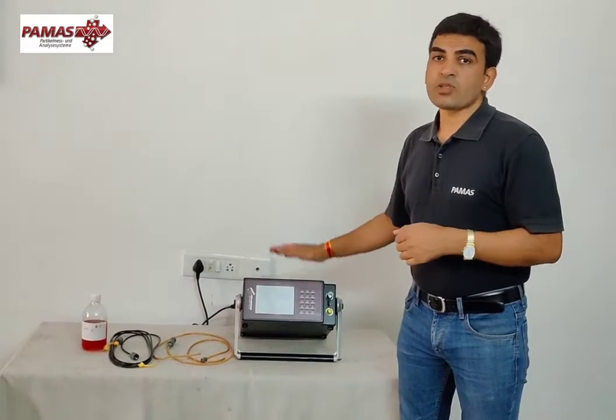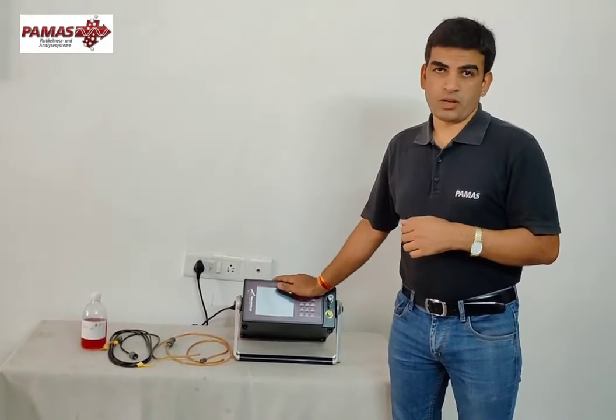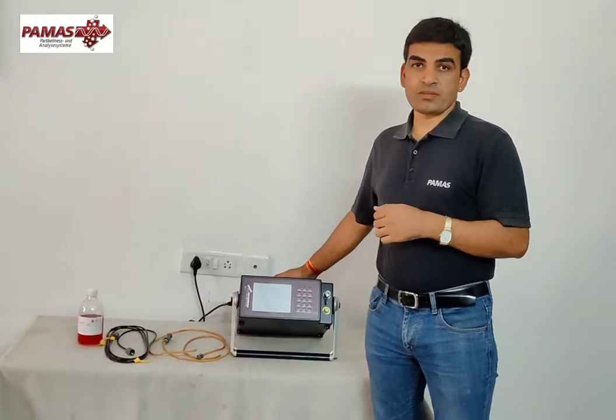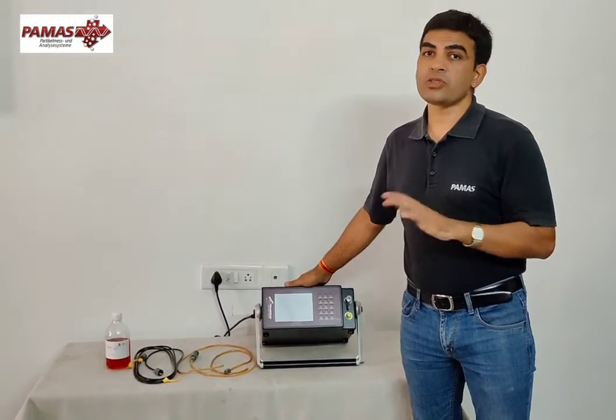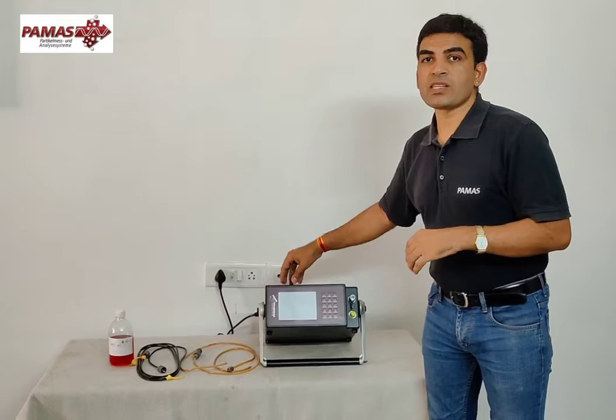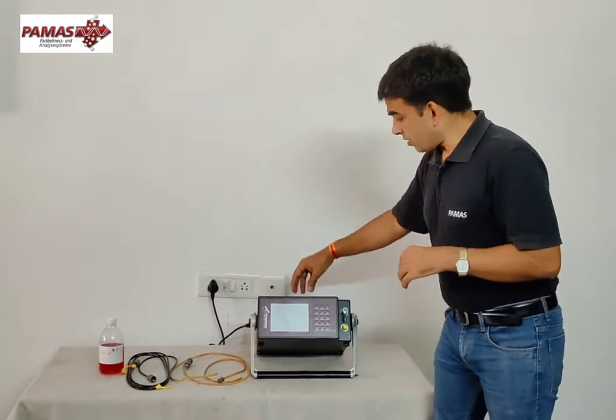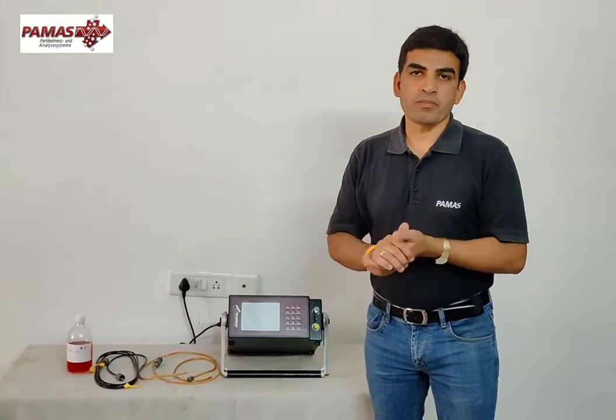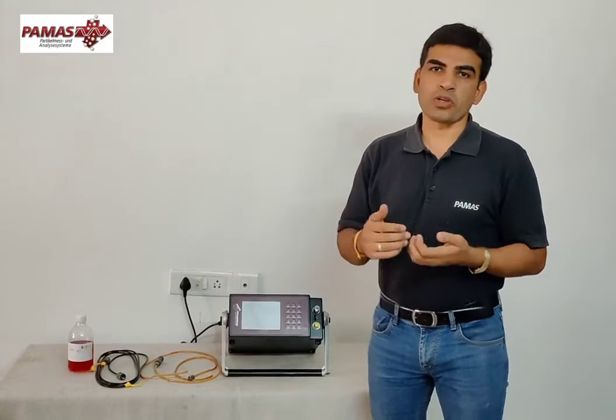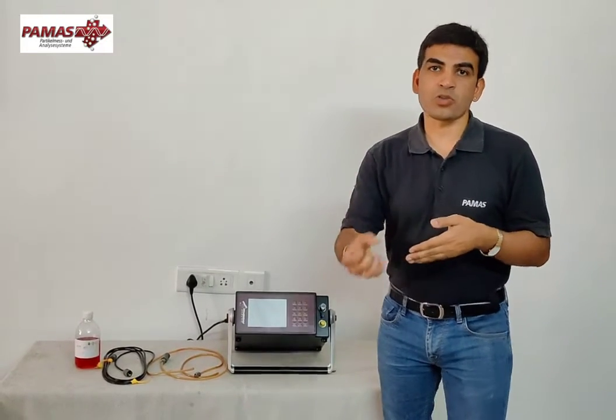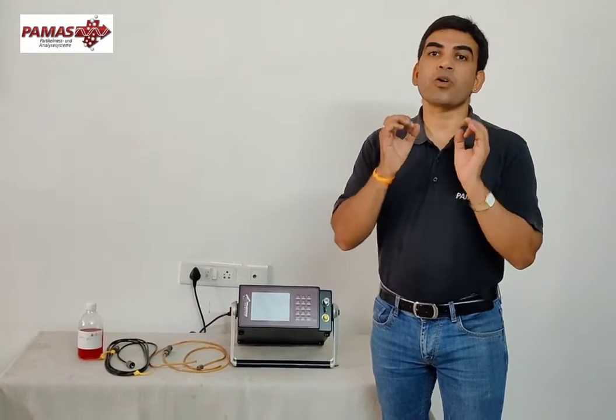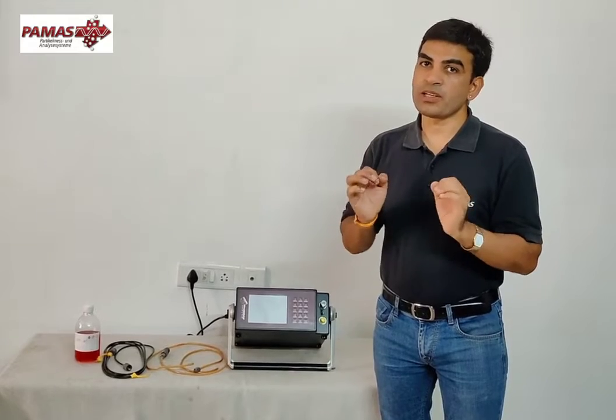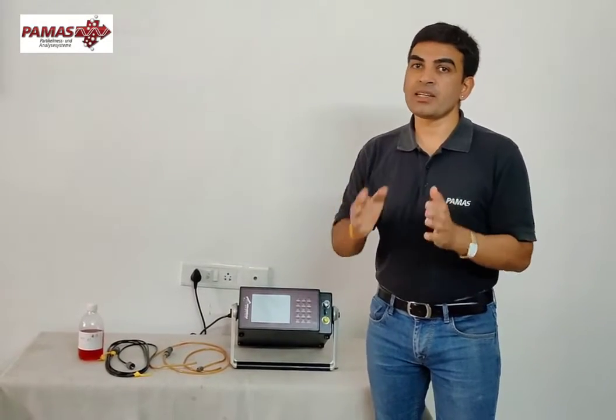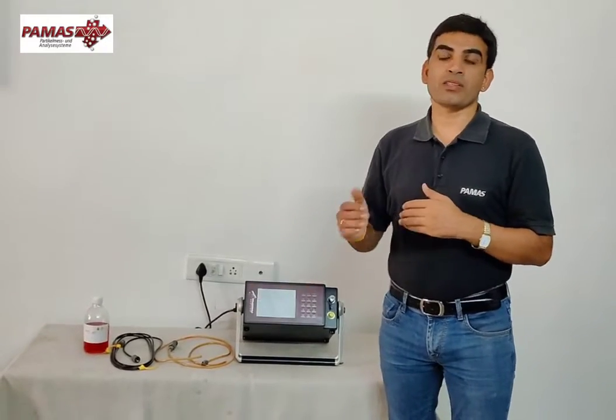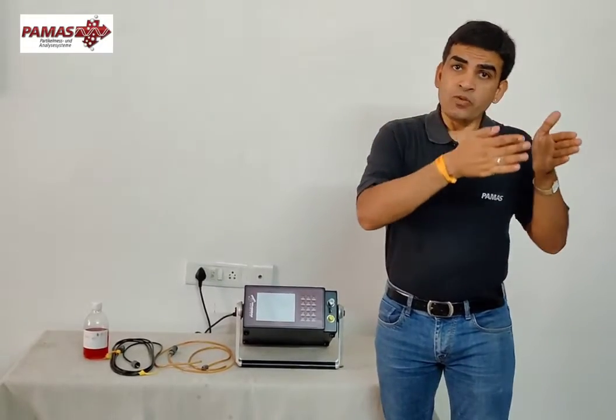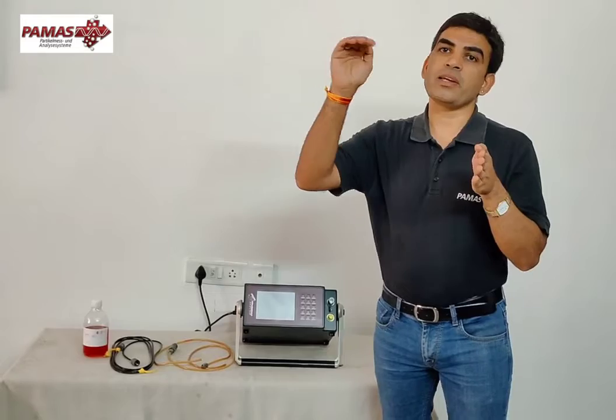Another thing is it has internal memory and there is no consumable required. It has an inbuilt thermal printer. Even if you run out of paper, you don't have to worry about the data, it will save all the data internally. Another good thing is it has an inbuilt metering pump. When you are doing a measurement from a bottle, you need not apply any external pressure. It will draw the sample automatically, and that pump ensures a constant flow rate. Without a constant flow rate, accuracy won't be there. The system is calibrated at the same flow, and all measurements also take place at the same flow. That's why, when we have a constant flow rate, the accuracy is very high.